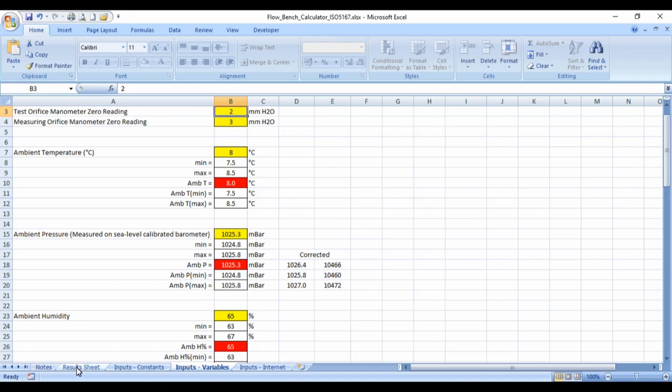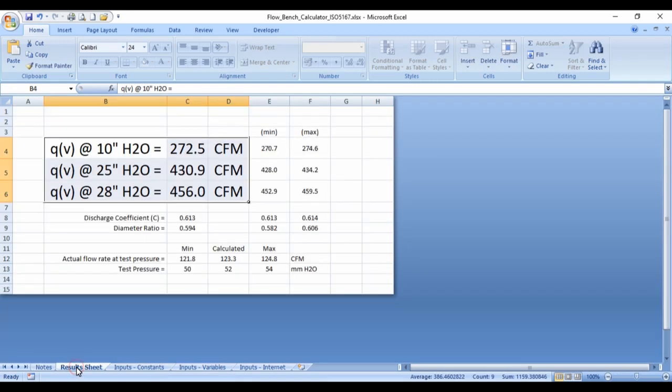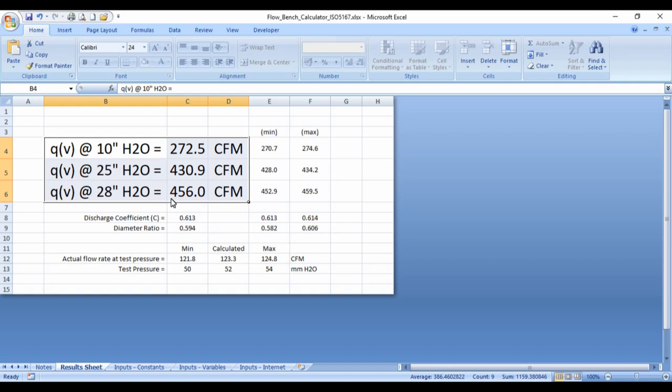We'll now go to the results sheet. And we can see that the actual flow rate was 123 cubic feet per minute. That gives an equivalent flow rate of 456 cubic feet per minute at 28 inches of water.